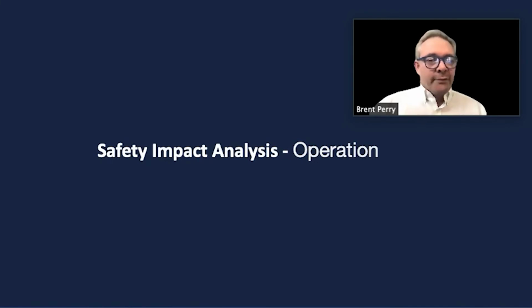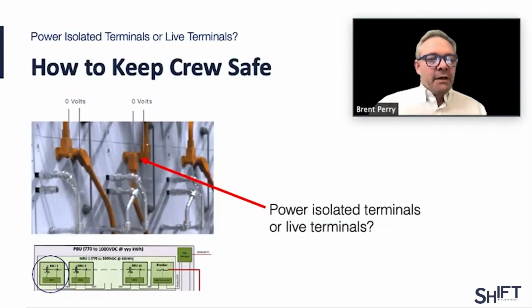Now, we look at the operations of the system. There are some simple things that we can do at the operating level to make sure that everybody is safe. In our case, we actually add contactors within each one of the modules to make sure that the positive and negative power terminals are completely isolated until the cables are all connected, and the BMS has actually determined that the sequencing of the cables is correct to prevent a dead short, and then it will allow the contactors to close and generate voltage and energy onto the grid of whatever it is we're connected to.